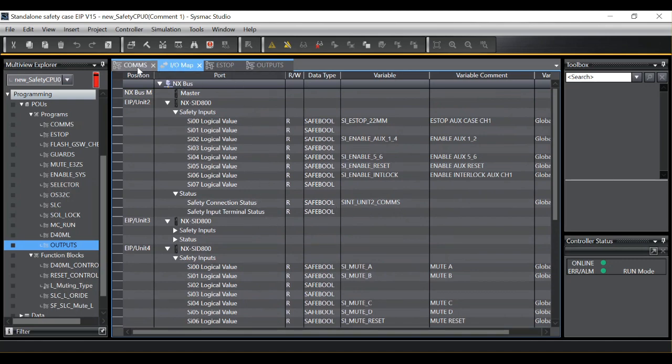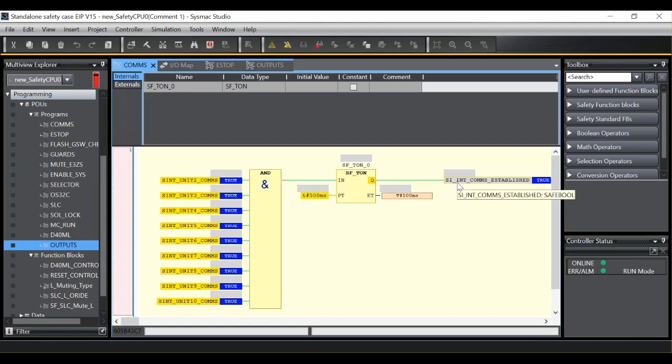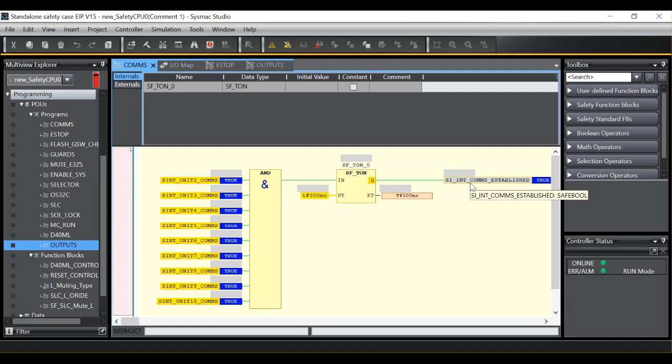I then have a section of my program called comms where I take the status of all of my IO into an AND block as you can see here. Use a timer just to add a 500 millisecond delay and then create a variable called in my case INT, SI INT, comms established.